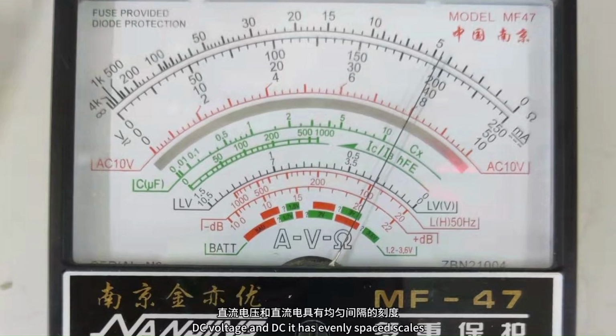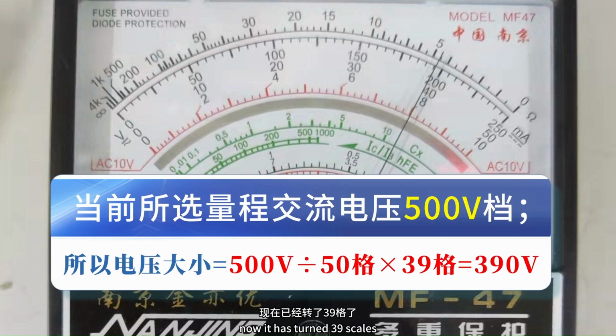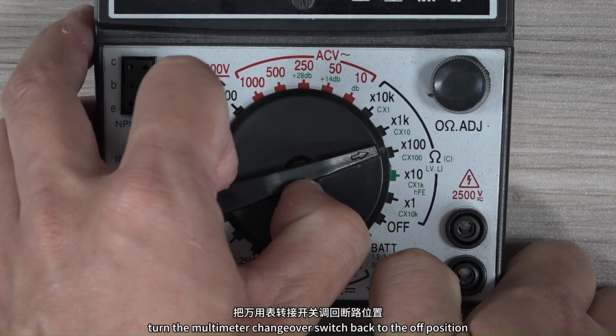DC voltage and DC current share it. It has evenly spaced scales. When reading, start reading from the left. When the pointer is at full scale deflection, the reading is the value of the selected range. Now it has turned 39 scales. The voltage is equal to 500 volts divided by 50 and multiplied by 39, which is 390. Measurement completed. Turn the multimeter changeover switch back to the off position.